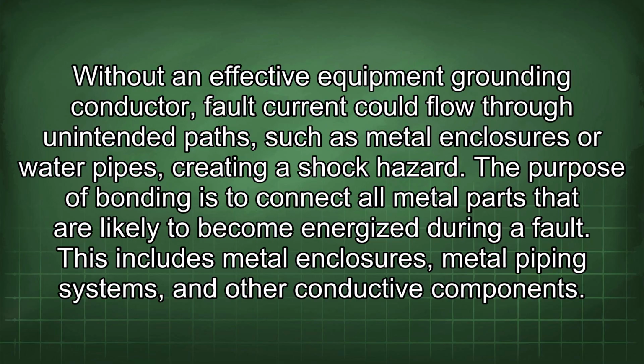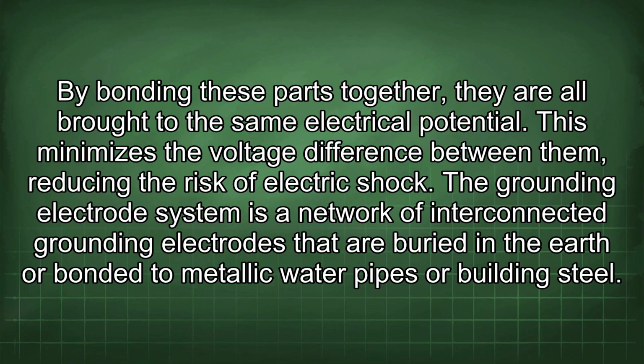creating a shock hazard. The purpose of bonding is to connect all metal parts that are likely to become energized during a fault. This includes metal enclosures, metal piping systems, and other conductive components. By bonding these parts together, they are all brought to the same electrical potential. This minimizes the voltage difference between them, reducing the risk of electric shock.